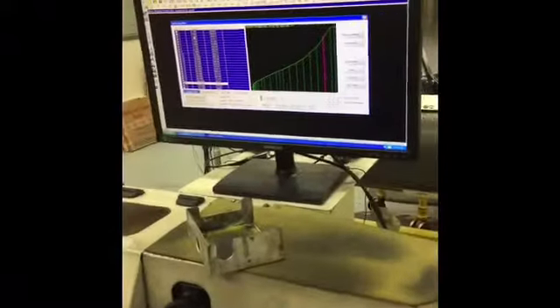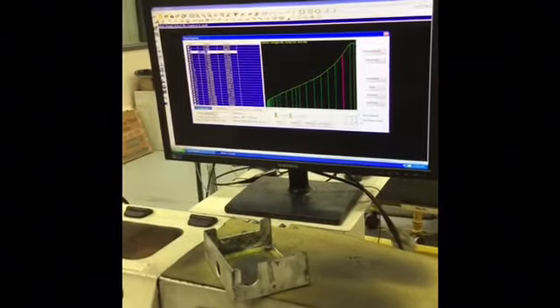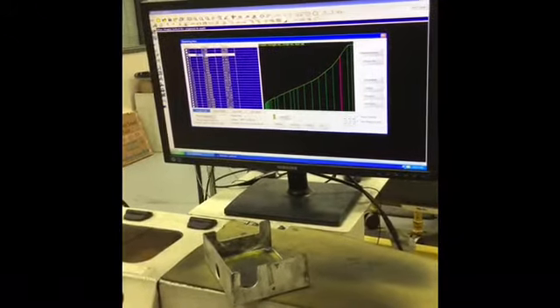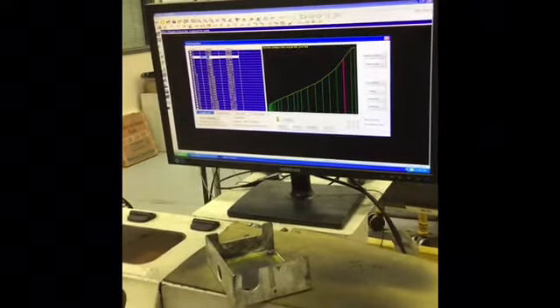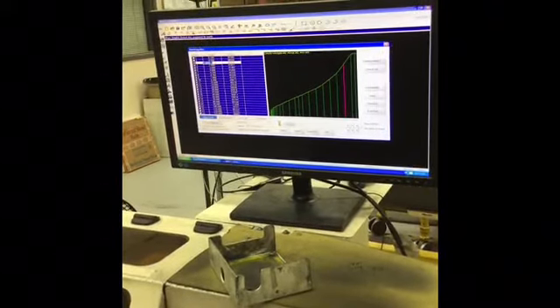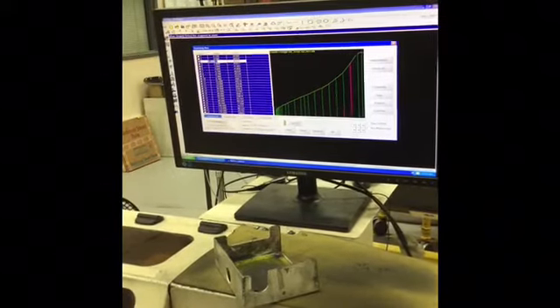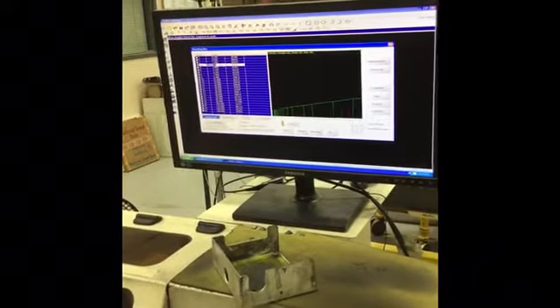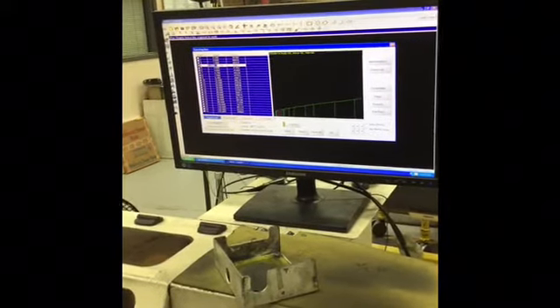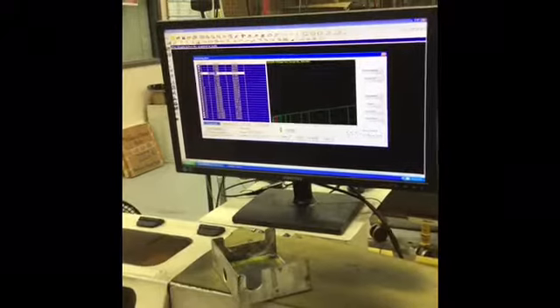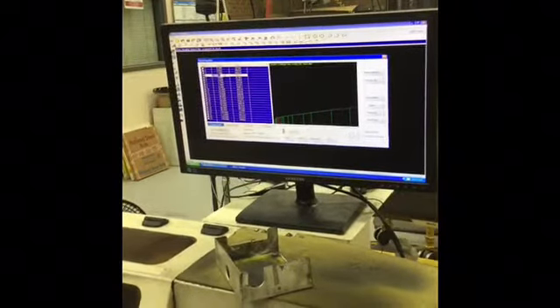So once you do that, on the first line, it says 1, you highlight it, and it shows what it's supposed to be, but then you type in what it actually was. So this would be, instead of 1 degree, it would be 0.2. Now it's changed, and you repeat the process per piece.